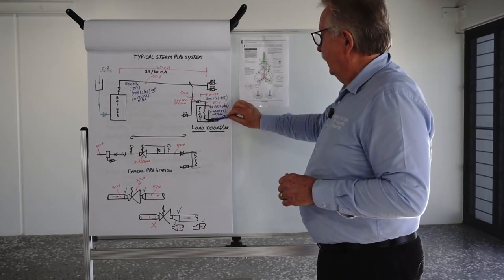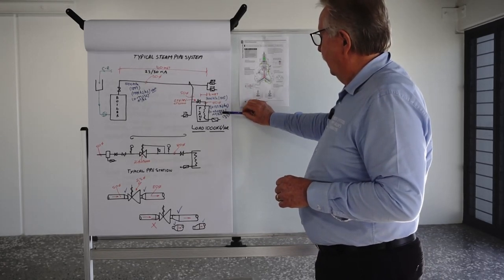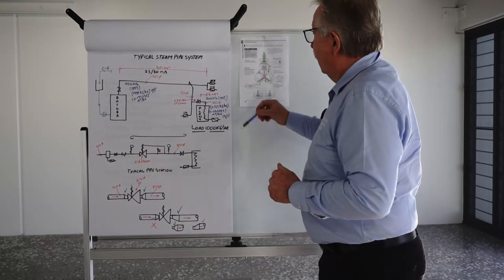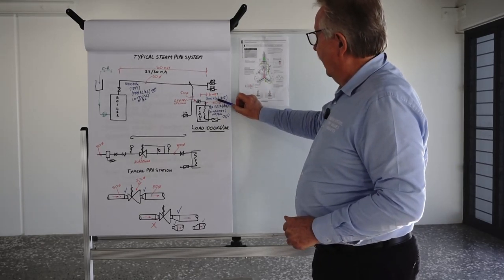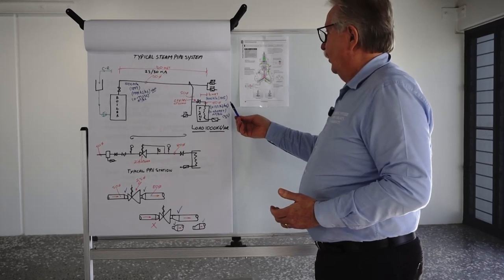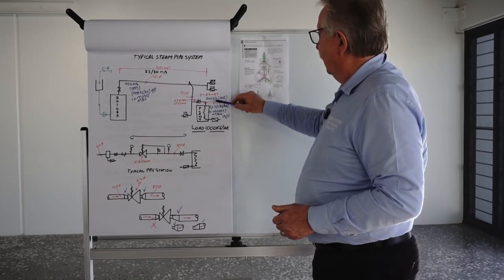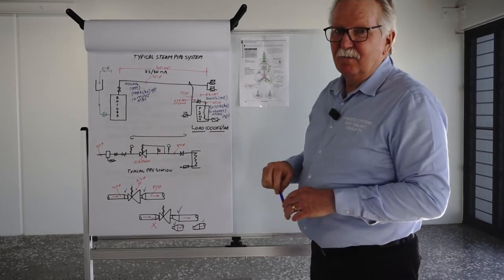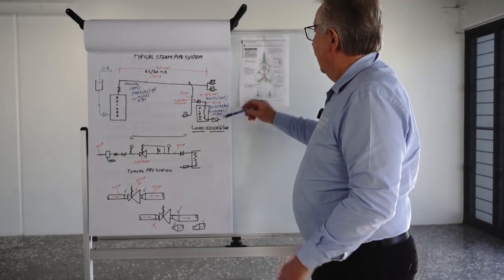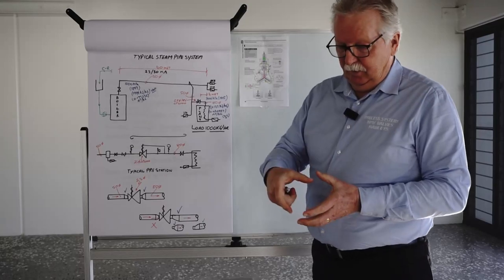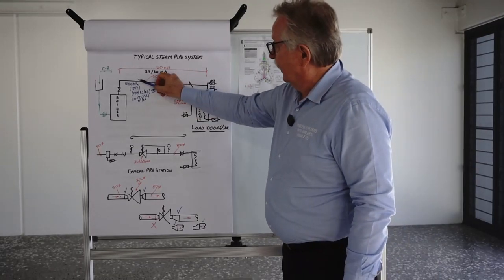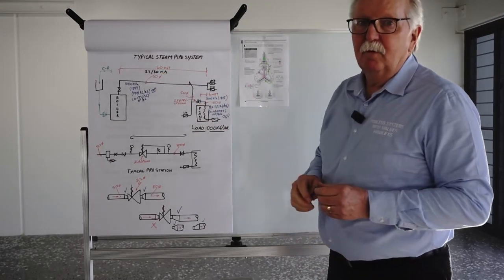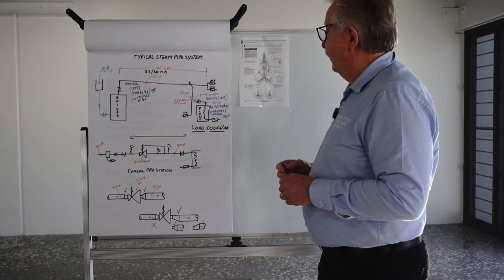Now after the PRV at 300 kPa and the increased specific volume, we would end up with a size again using 25-30 metres a second roughly, it's only a short run of pipe, I've elected it to be about 6 metres of pipe. We would end up with an 80 mil pipe, so we've got a 50 mil here and an 80 mil nominal bore pipe at the point of usage.